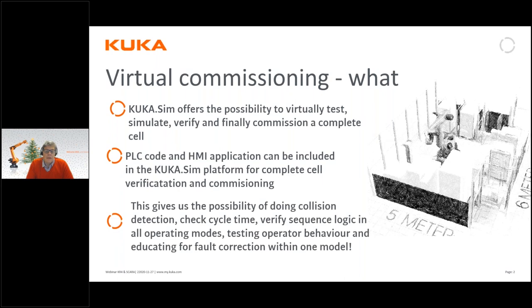KUKA.Sim also gives us the possibility of doing collision detection and checking cycle time. Using all these codes together we can verify sequence logic in all operating modes. We can use the HMI together with KUKA.Sim and test operator behavior. Usually the programmer of the HMI expects the operator to behave in a certain way, and perhaps that is not the case. We can even use this model to do operator training before the cell actually exists.